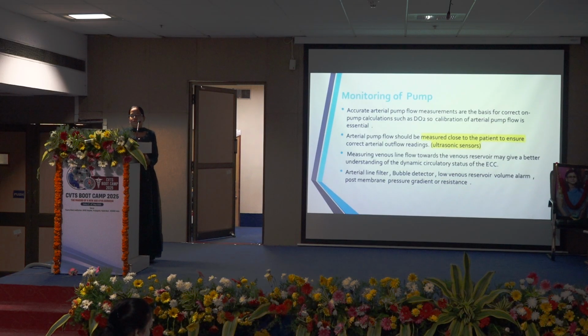So accurate arterial pump flow measurement is the basis for correct on-pump calculation. Where you are calculating the pump flow is more important. Basically, with ultrasonic sensors you can calculate the pump flow, but theoretically it should be measured as close to the patient level as possible to get the correct value. Similarly, you can measure the venous flow, which will give you the fluid dynamic circulatory status in the extracorporeal circulation. And different safety features of the pump, like arterial line filters, bubble detector, and venous reservoir alarm, should be used whenever available.